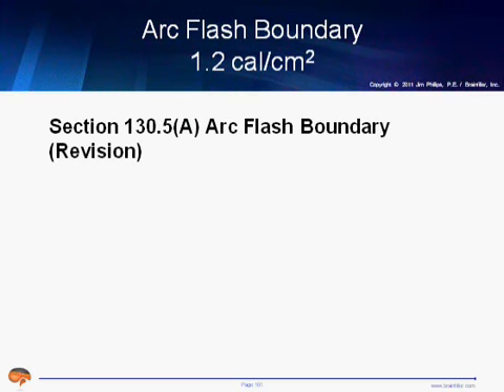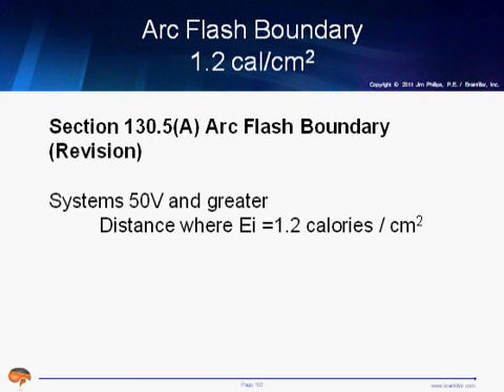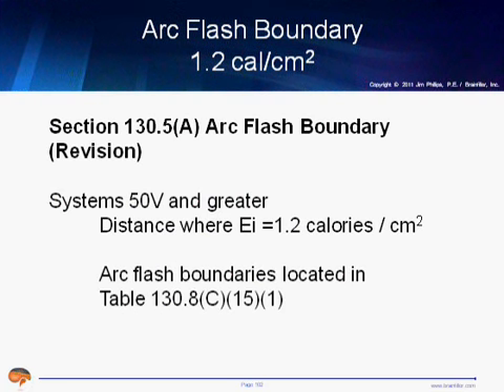Well, beginning with the 2012 edition of NFPA 70E, the arc flash boundary is going to be the distance where you reach 1.2 calories per square centimeter, period, unless you use the hazard risk tables. And then there will be boundaries that are included within the different hazard risk tables.